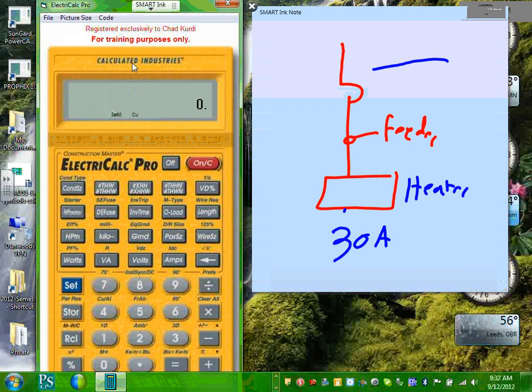So here's my question for you. I have a 30 amp heater, 3-phase. So I'm going to go set my terminations. My terminations. Do you guys hear me? So let's say it's 3-phase. This heater is 3-phase. I want to put my termination to 3-phase. So set 3-phase. I'm set for 3-phase, and I need to set 75. Okay. So if I have a heater, 3-phase stuff, guys, almost always rated for 75. So I have a heater rated for 75. It's 30 amps, and I need just to size a conductor for it.